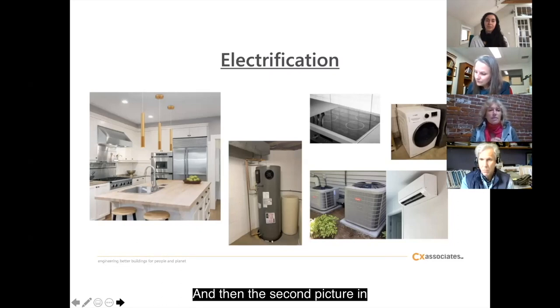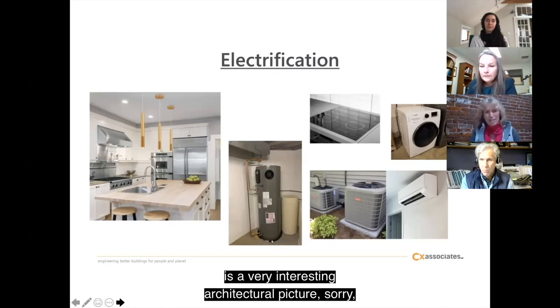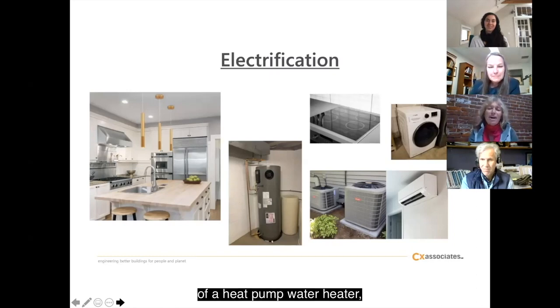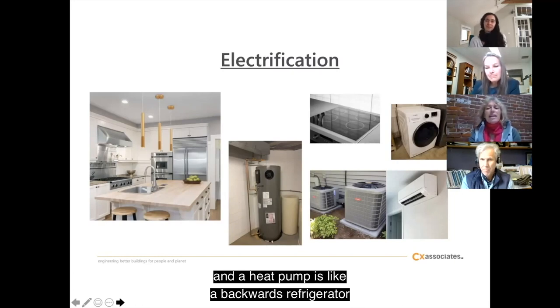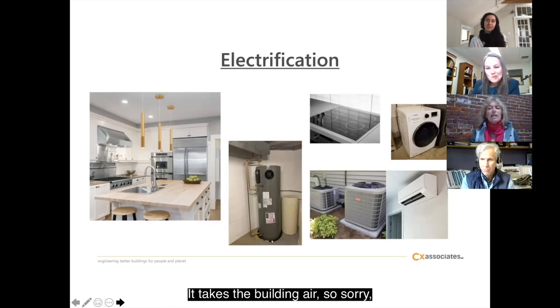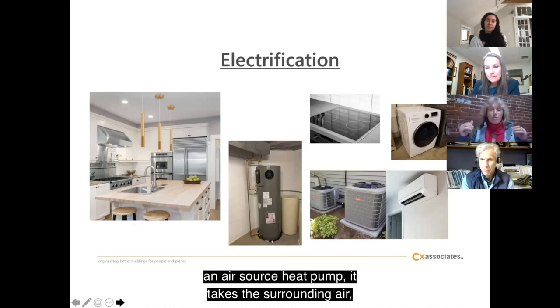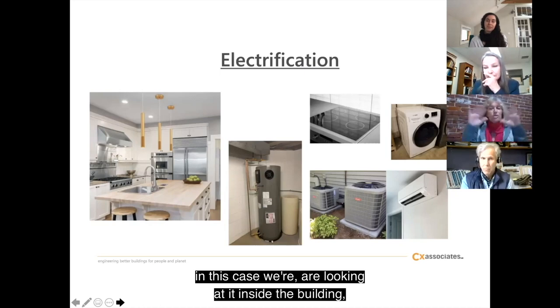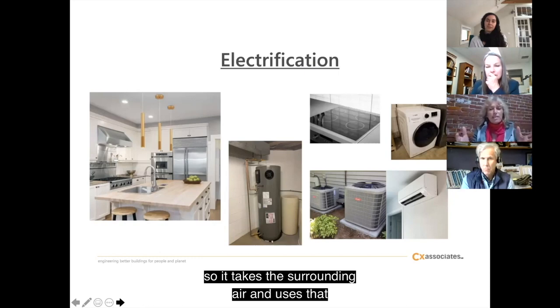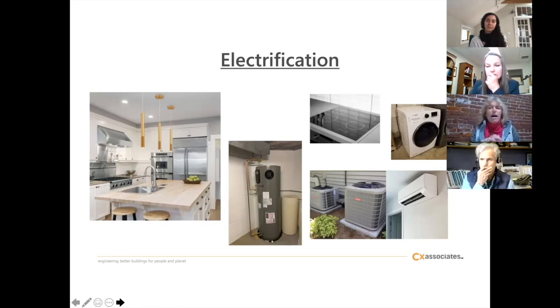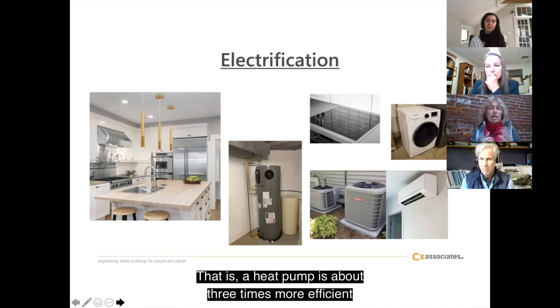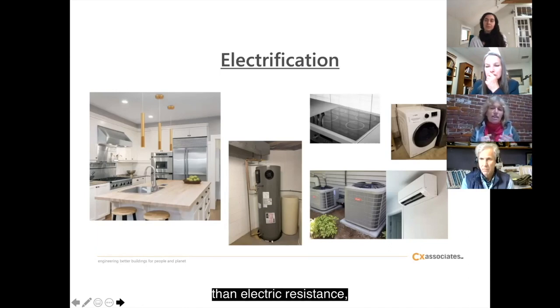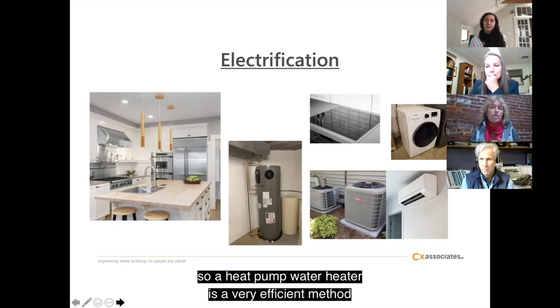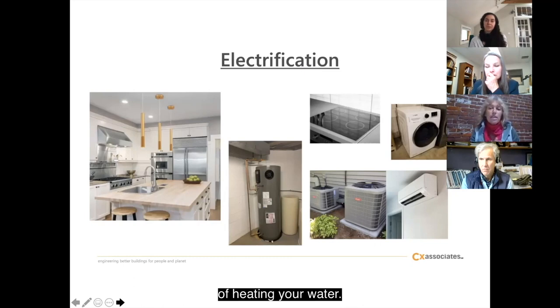And then the second picture in is a very interesting architectural picture of a heat pump water heater. And a heat pump is like a backwards refrigerator, if you will. It takes the building air, an air source heat pump. It takes the surrounding air, in this case, we are looking at it inside the building. So it takes the surrounding air and uses that to heat the water. That is, a heat pump is about three times more efficient than electric resistance. So a heat pump water heater is a very efficient method of heating your water.